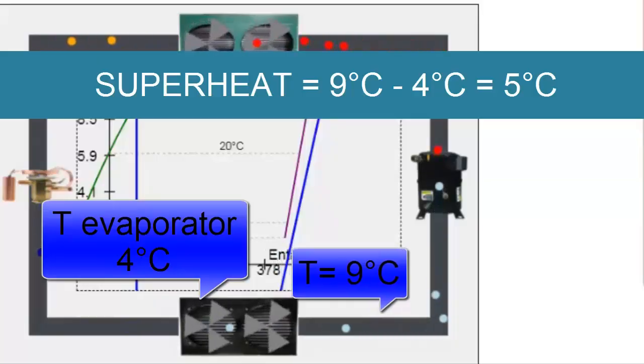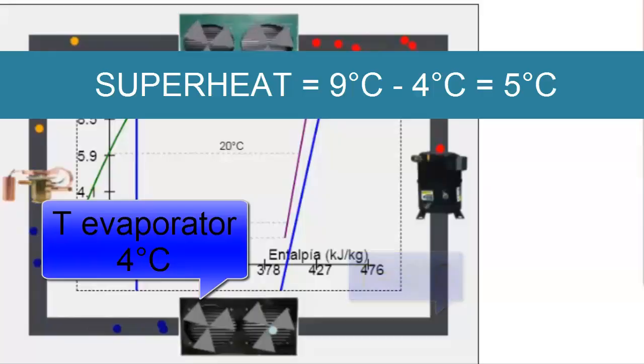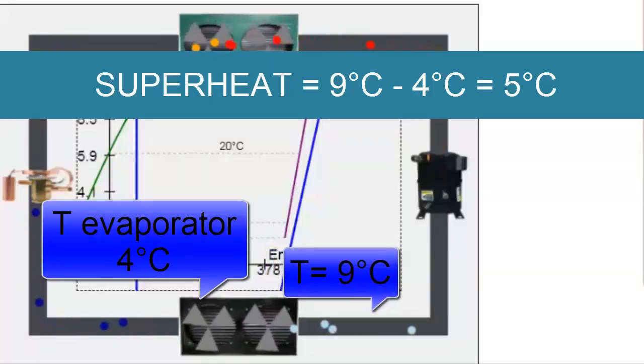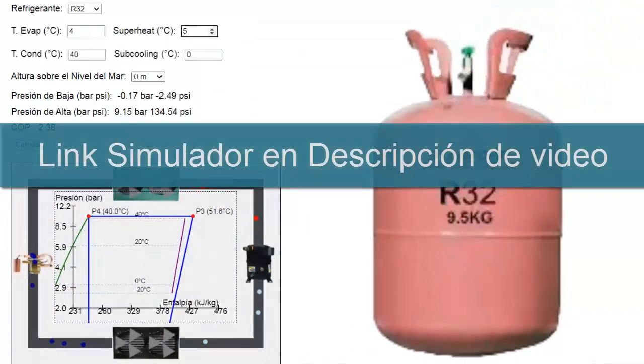On the other hand, with a lower thermal load or fewer people in the room, the superheat will be less than 5 degrees Celsius, and can even reach 0 degrees Celsius when the cooling load is very low.